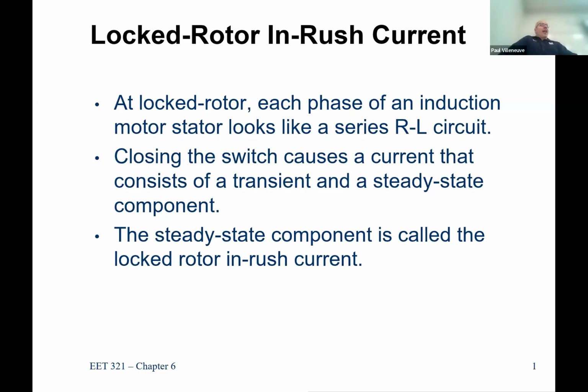And if you actually look at the protection characteristics for a motor, they actually are designed so that under short time frames, 5, maybe 10 seconds or less, you actually can start your motor. You can pull a lot of current in, but after 5 or 10 seconds, then you should be at your normal full load amps. So you don't want to indefinitely allow that large amount of current, unless, again, we talked about the fire pump, right, when you had that application.